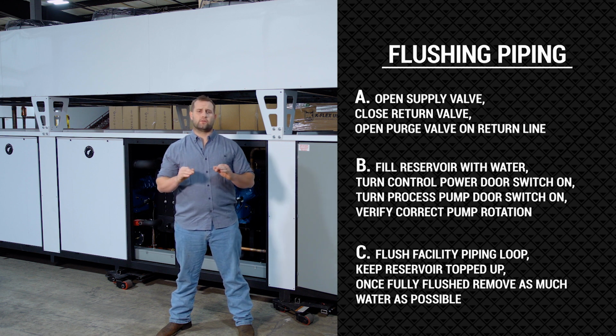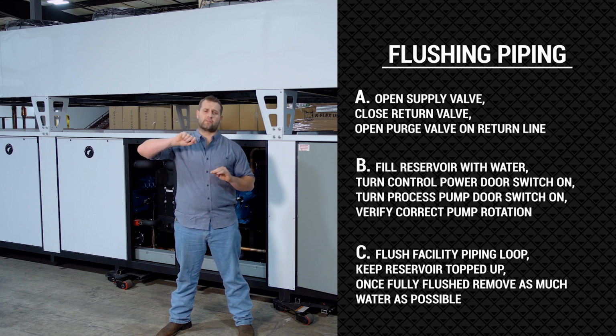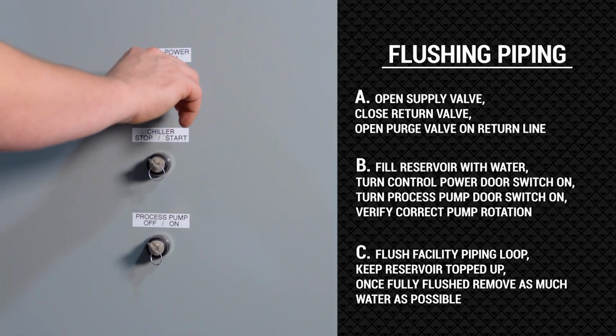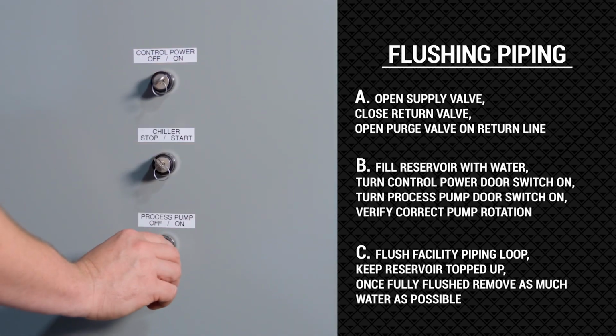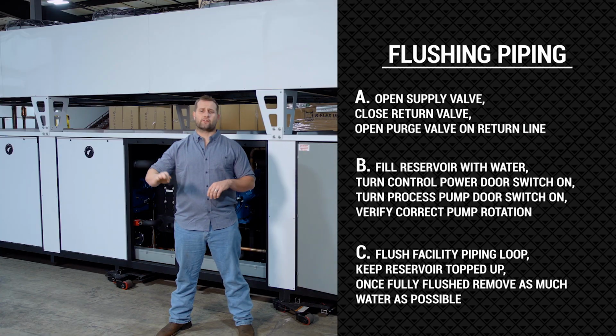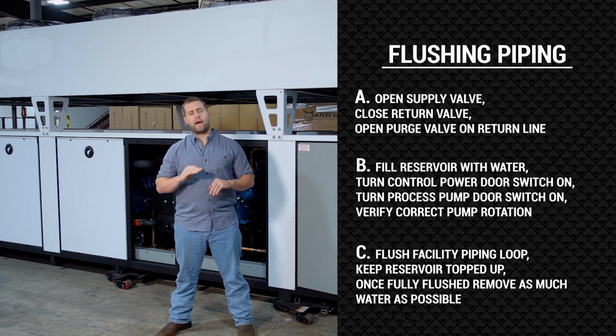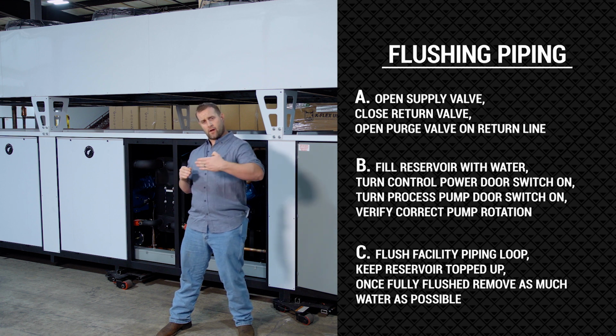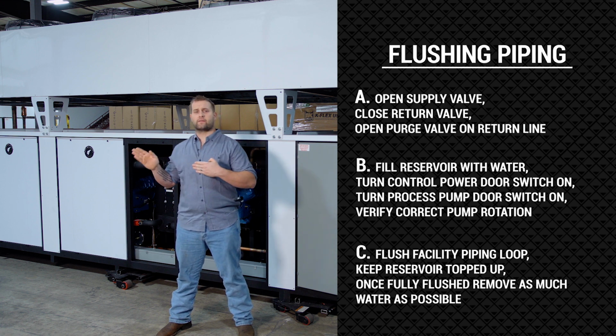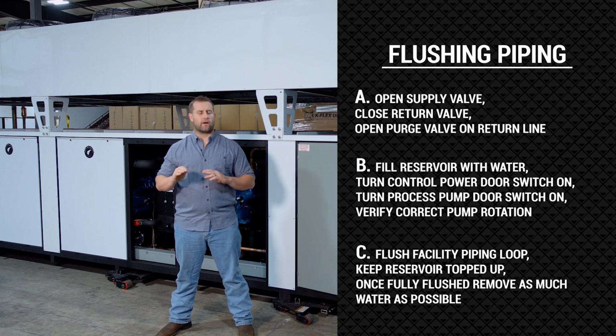So you would fill the reservoir full of water, go to the control panel, and make sure your compressor breakers are off. Then turn the control power door switch on, and turn your process pump door switch on. That starts the process pump, and you start circulating water throughout your process. It's a good opportunity at this point to check your process pump rotation. From the back, it's going to be clockwise. If you're looking from the front, from the volute to the back of the motor, it's going to be counterclockwise. Once that's verified, run water until the water coming out of the Y strainer is nice, clean, and clear.